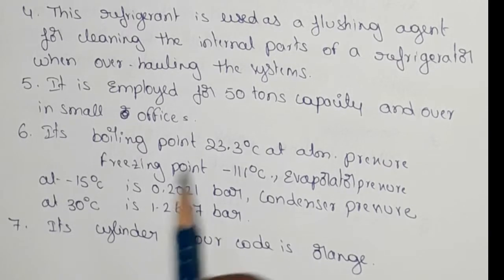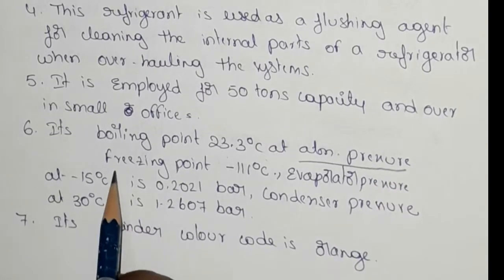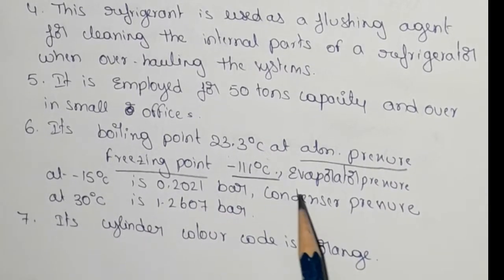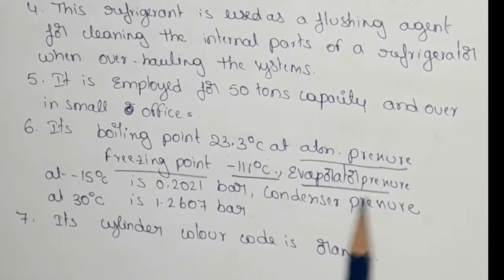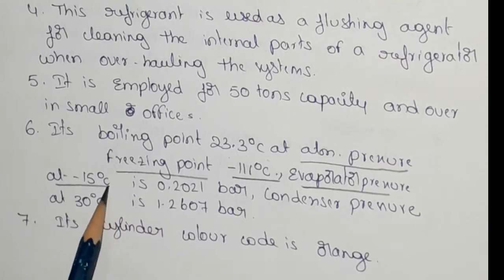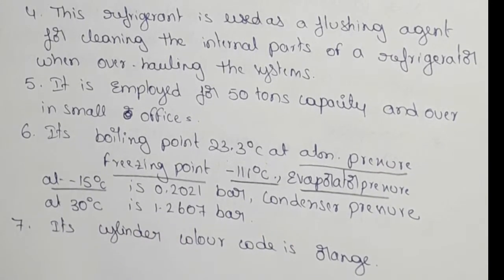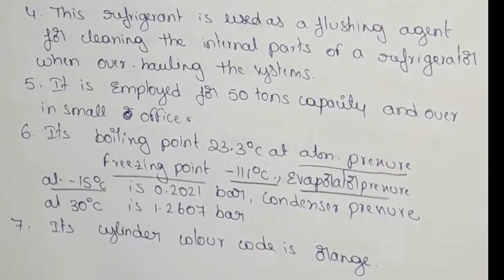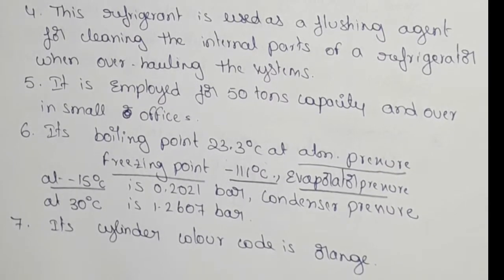The boiling point is 23.3 degrees centigrade at atmospheric pressure. Freezing point is minus 111 degrees centigrade. Evaporator pressure at minus 15 degrees centigrade is 0.2021 bar. Condenser pressure at 30 degrees centigrade is 1.2607 bar. We maintain these temperatures.